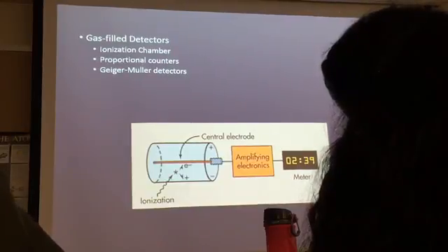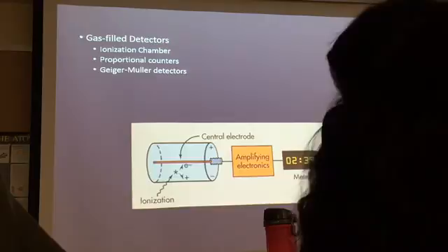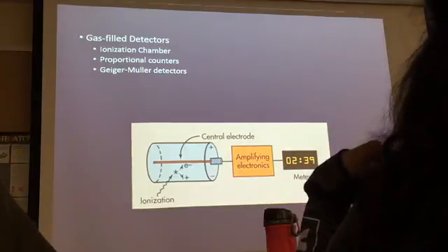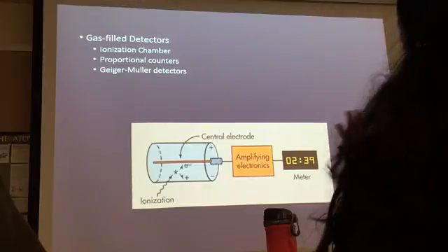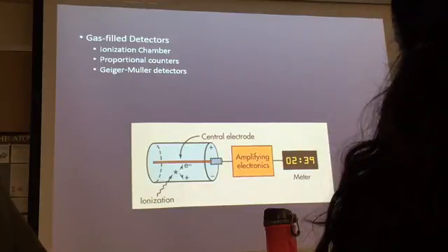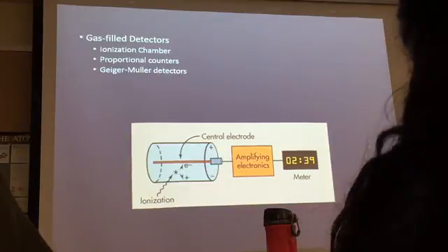You can put one right in front of a radioactive compound that is emitting betas or alphas and it's not going to detect them. It just doesn't happen. So you need to make it more sensitive, and when I say more sensitive, what am I saying? Increase the voltage. When you increase the voltage, now you can start detecting alphas and betas. And as you go on.